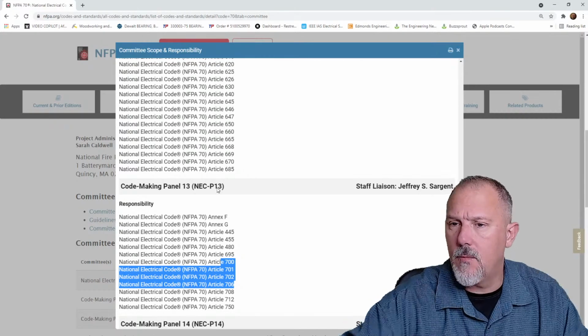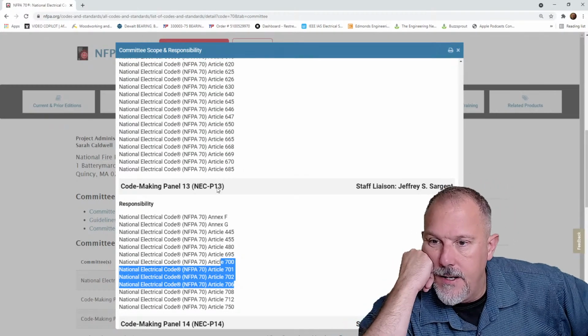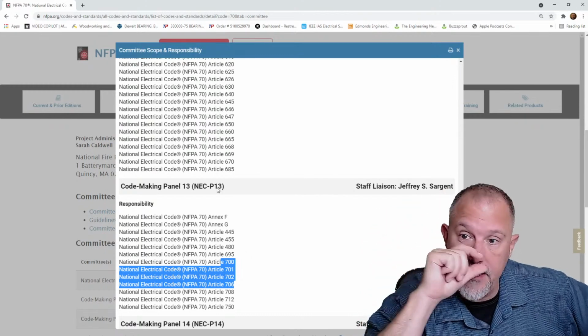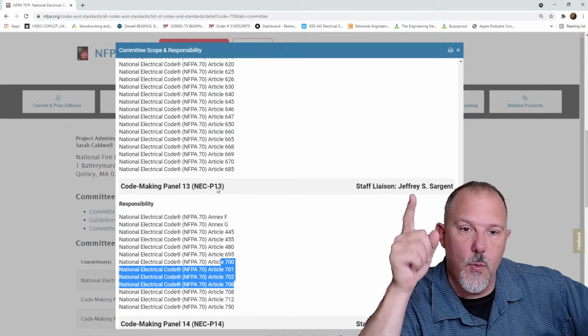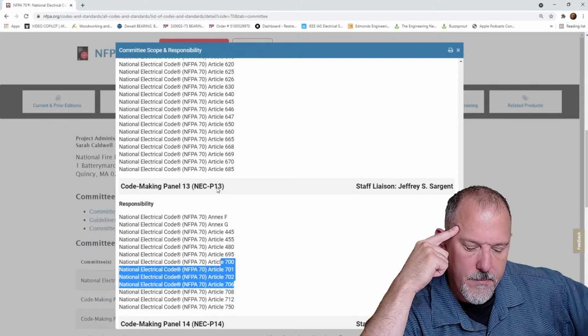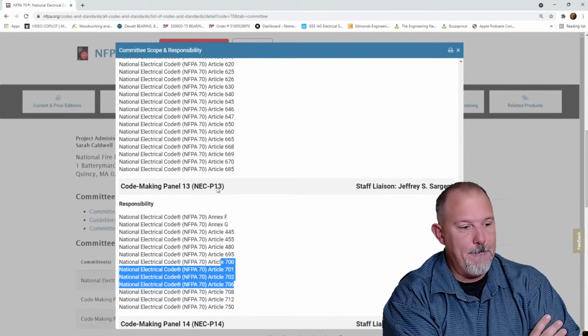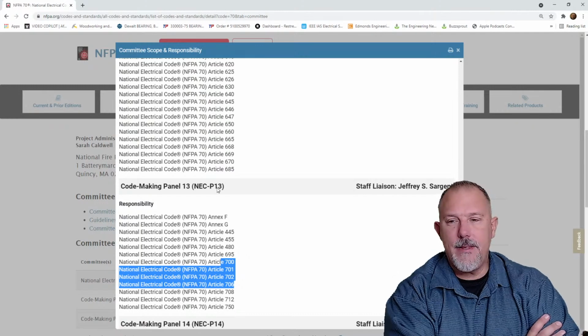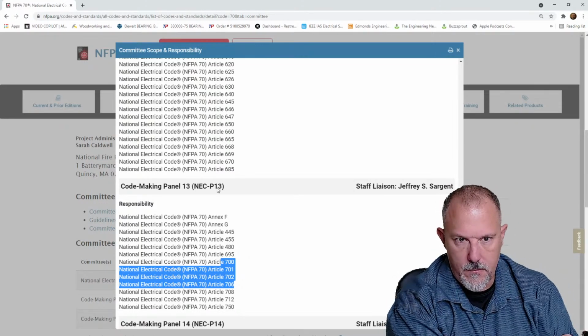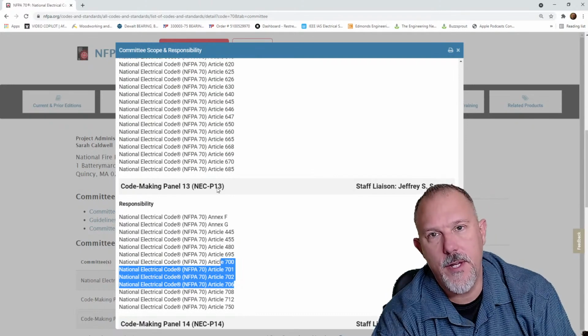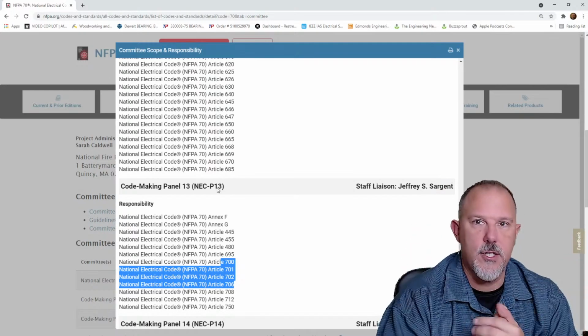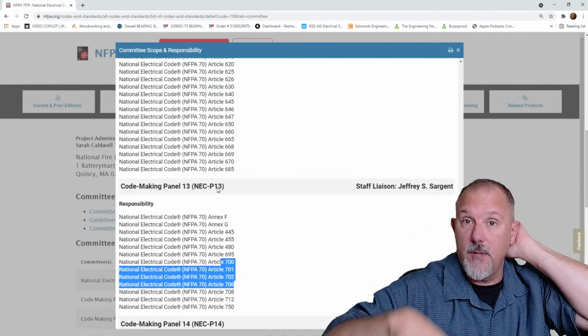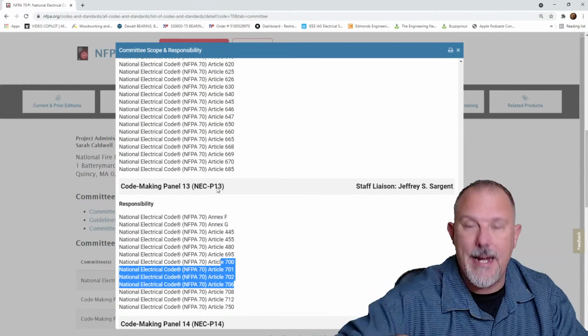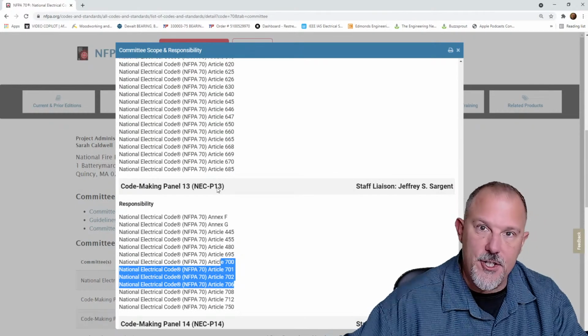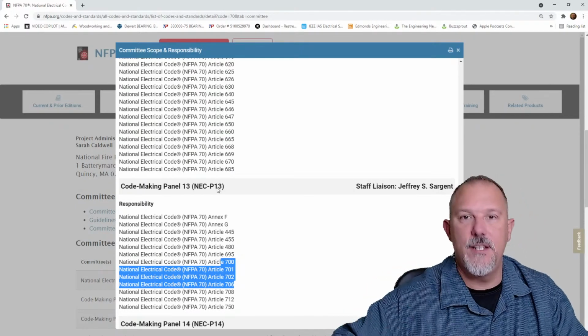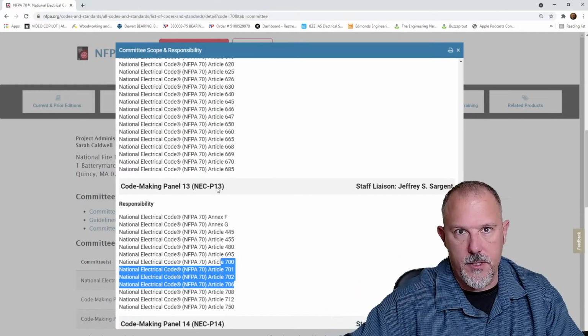So Ryan says he thinks it should be in 240. And I agree with you, Ryan. I think there's value in the signage. And here's the issue with 240. Remember, well, that's a good point. But here would be my only concern, Ryan. 240 is not a labeling; it's an overcurrent protection thing, right? 700 has the requirements for selective coordination, and if you put it, I know it's multiple times, but if you put it in each, then where the requirement is for selective coordination, you have the labeling requirements.